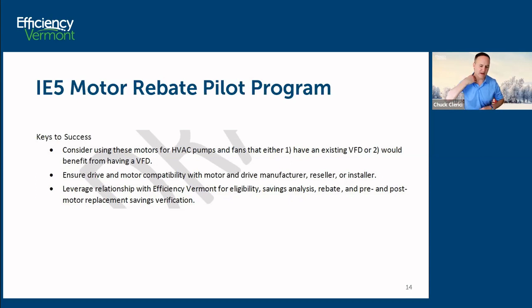But if that drive's only been out there for a short amount of time, we'll have a little bit of an extra hurdle. I won't ever say no. We'll always go to bat for what we believe is a good savings project. In your example, if the new motor requires a new drive, I think we would go to bat for that with the department, explain the situation, and try to appeal to a higher sense of efficiency. That's the only way that motor is going to get in there, is with a new drive in that example.